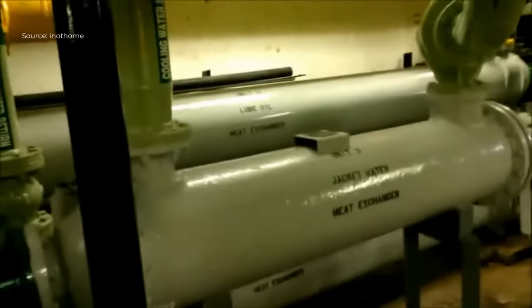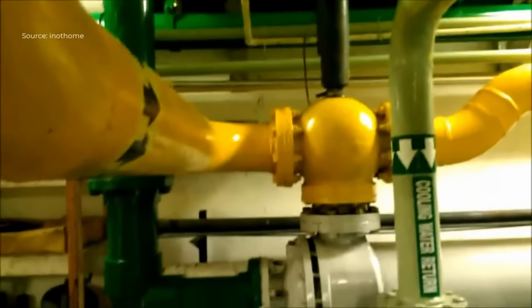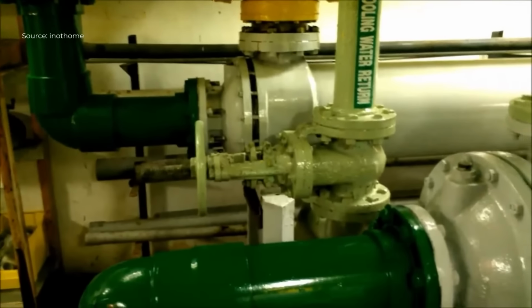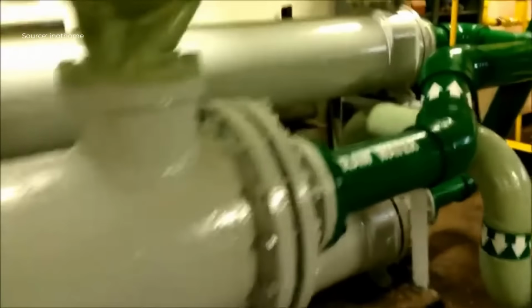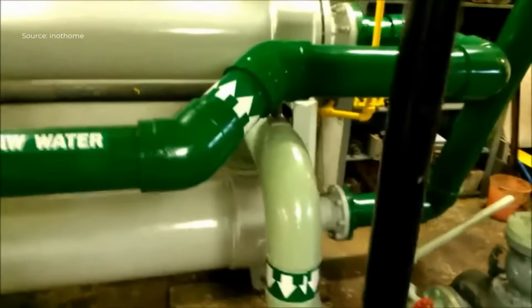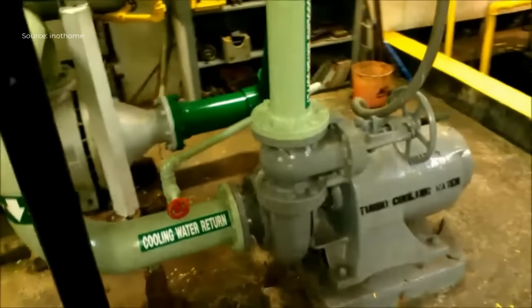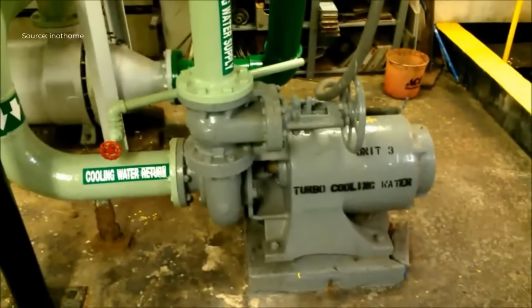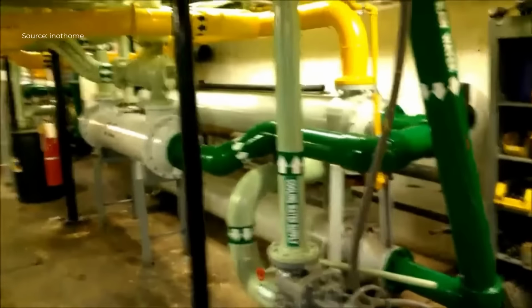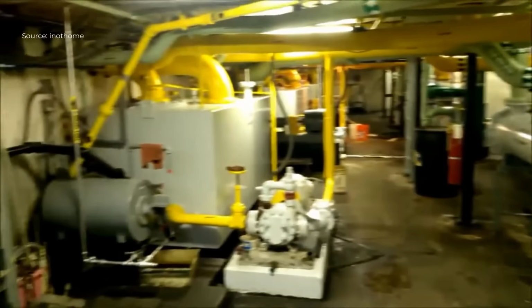At the heart of the system is a large V-configuration diesel engine with 16 cylinders operating on a 4-stroke combustion cycle. This design allowed for smooth power delivery, excellent torque characteristics, and long service life. The engine was rated at an impressive output of 3 megawatts, although in typical operation it runs at around 2.5 megawatts, ensuring reduced stress on components and increased reliability during continuous duty. Such conservative operating practices were common in mid-20th century power plants, where longevity was valued over maximum output.